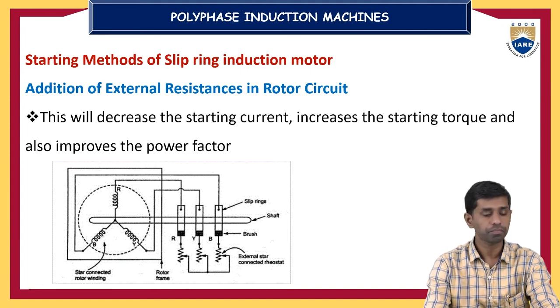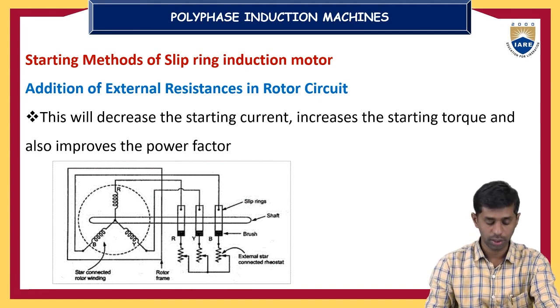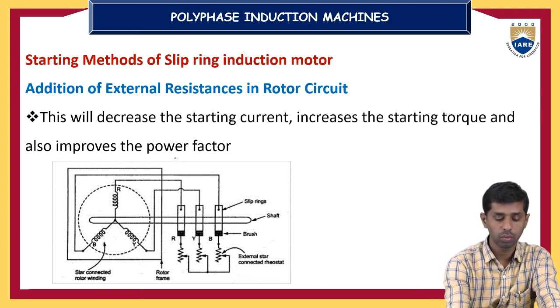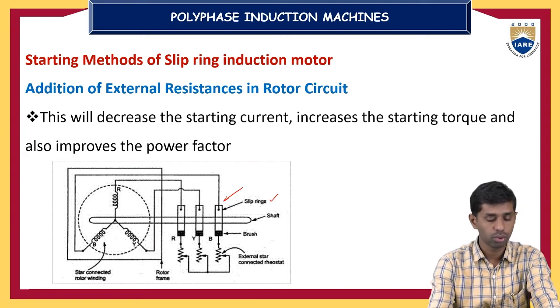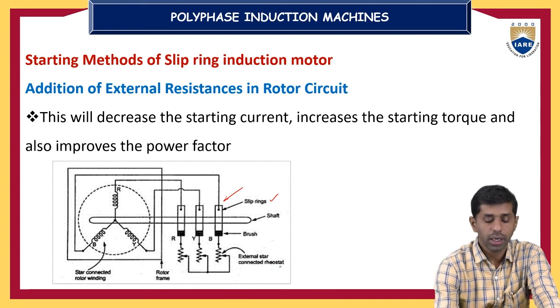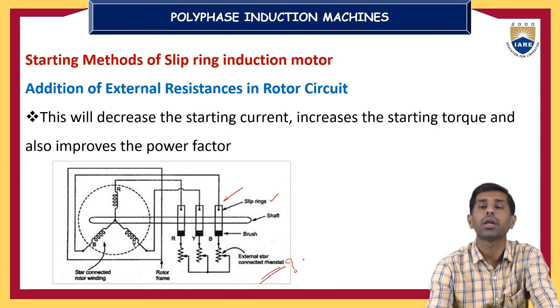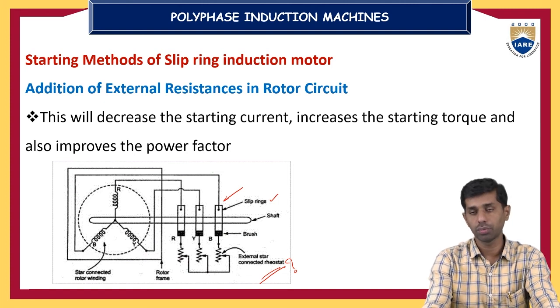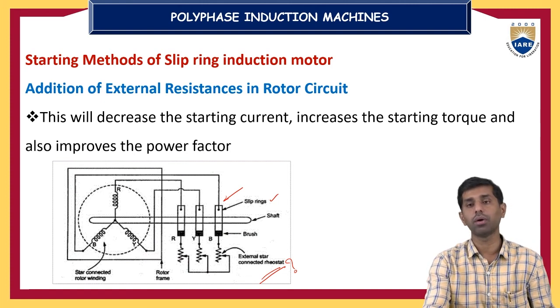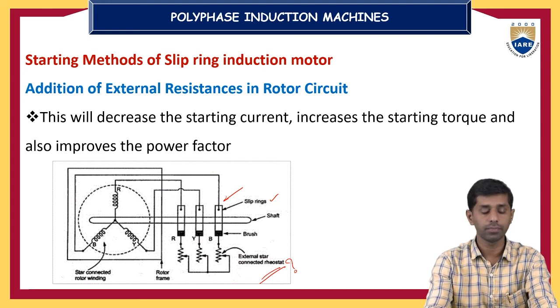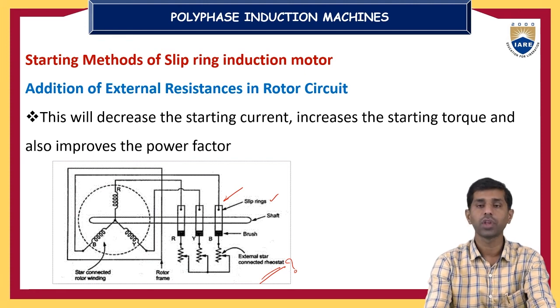But in the case of the slip ring induction motor, here I am giving a star connected rotor winding which is connected to the 3 slip rings. These are the slip rings we have, and each slip ring is connected through brushes. We can connect external resistors, or an external load, to the slip ring induction motor rotor. So we can extract the energy from the rotor, whether it is connected to an electrical load, or we can connect external star connected rheostat banks into the rotor winding to increase the resistance of the rotor.